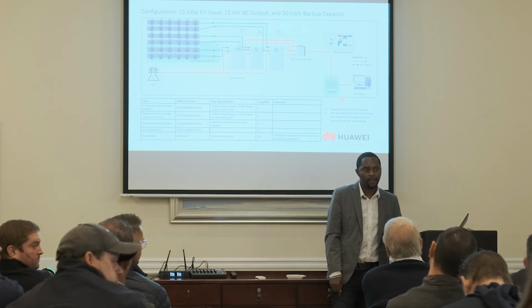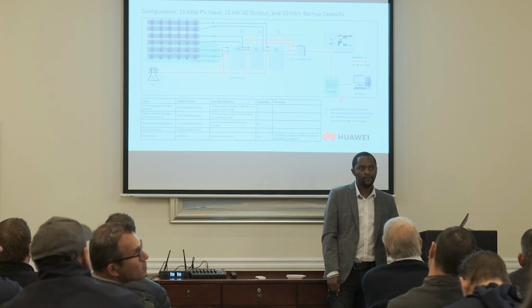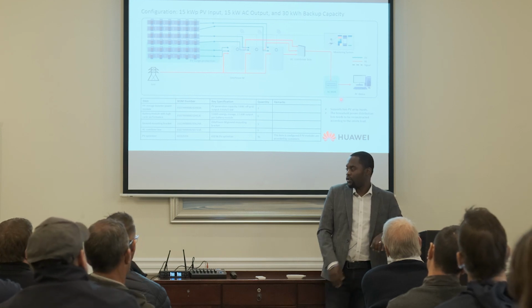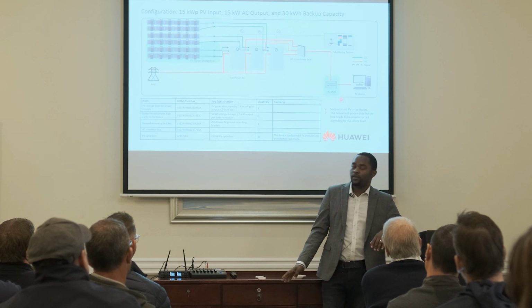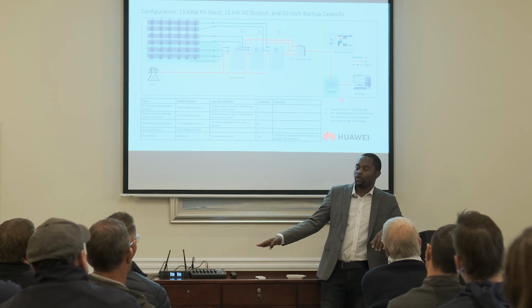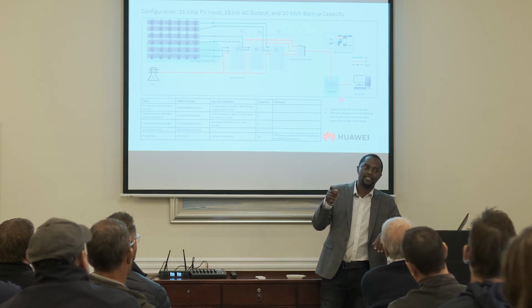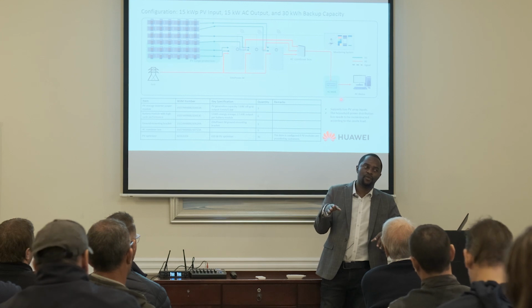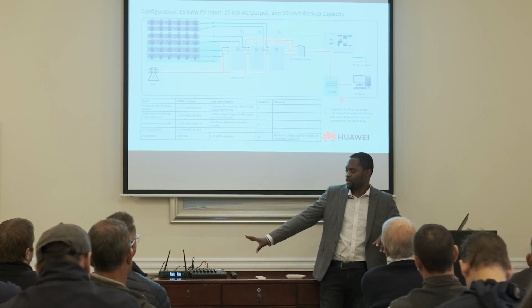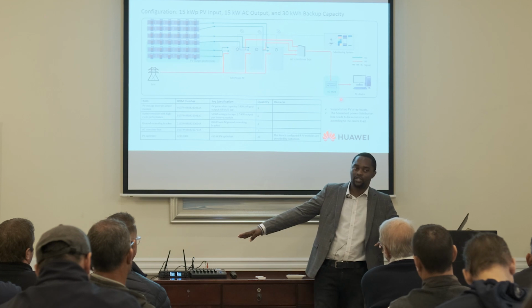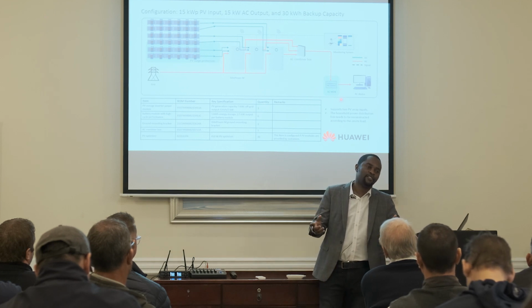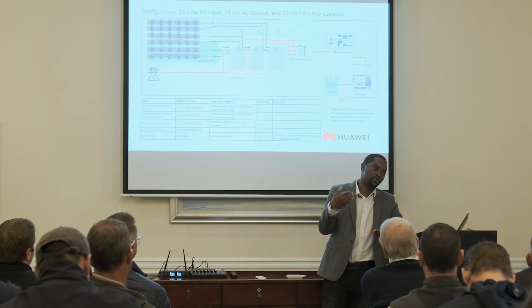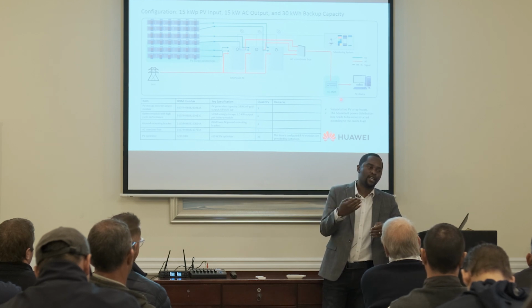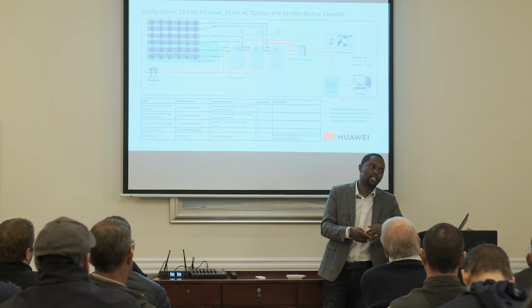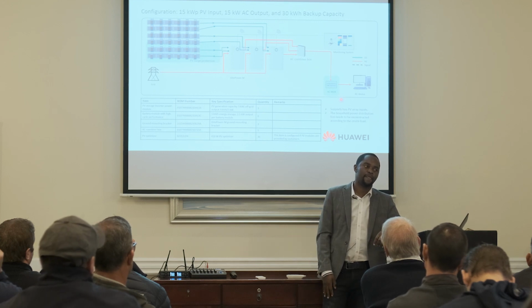If you've got a fault on one of the battery modules, will it isolate? So can you isolate the module besides physically taking it out of the system? If we've got a fault on one of the modules, it actually goes into bypass, which is a good thing, like all the Huawei systems. Let's say we've got 2 batteries and battery number 1 has a fault: you only lose that 5 kilowatt, but the other 5 kilowatt you are still using. Then Fusion Solar gives you an alarm that there's a fault, and you can go and attend to it while you still have power.